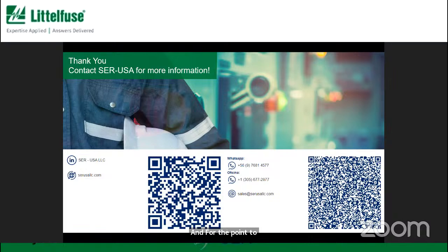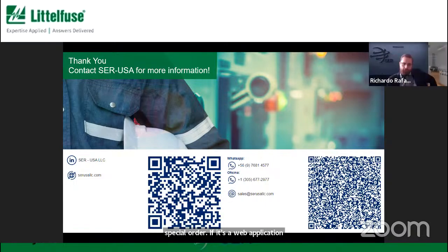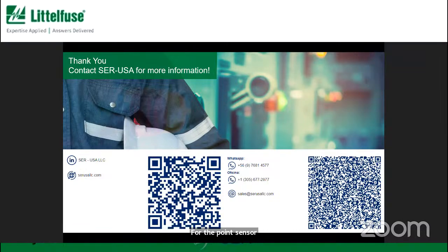Now, if you have an application where it is very wet, we have the ability to take the point sensor and cover it with a full coating of conformal coating. Then it would be suitable to be used in a very wet location. That is something we can do, but that would be a special order if it's a wet application. Oh, but it's possible from factory to ask it this way. For the point sensor, yes, that's correct.